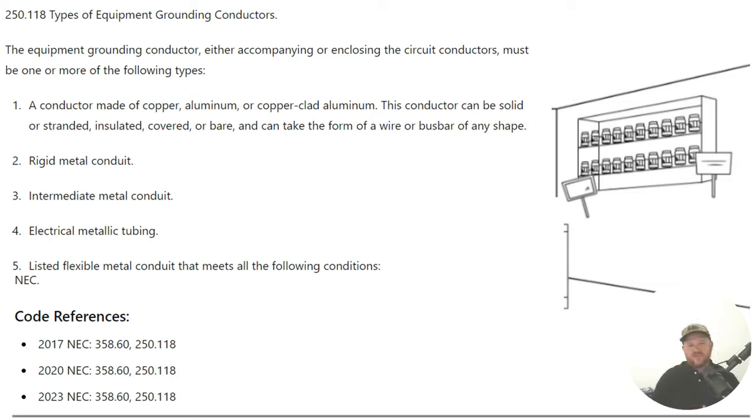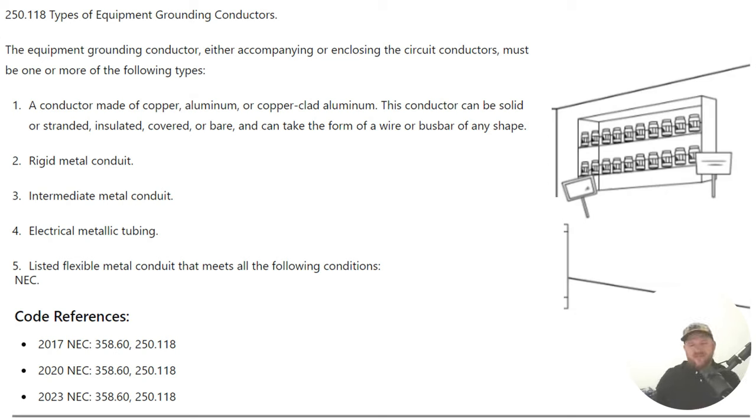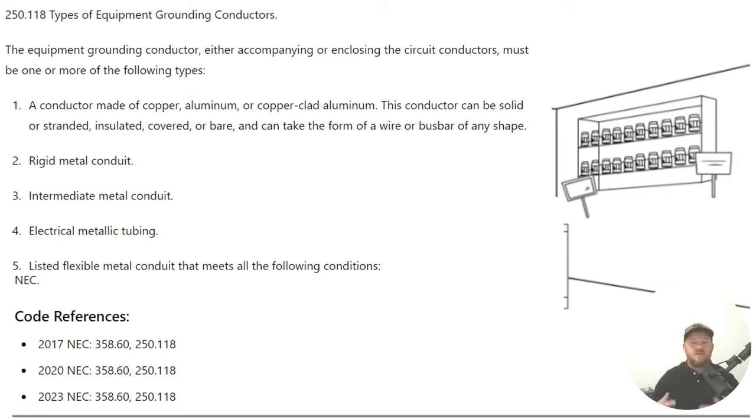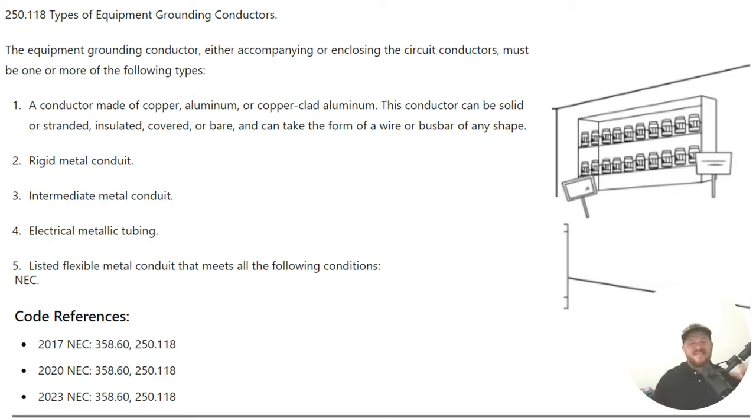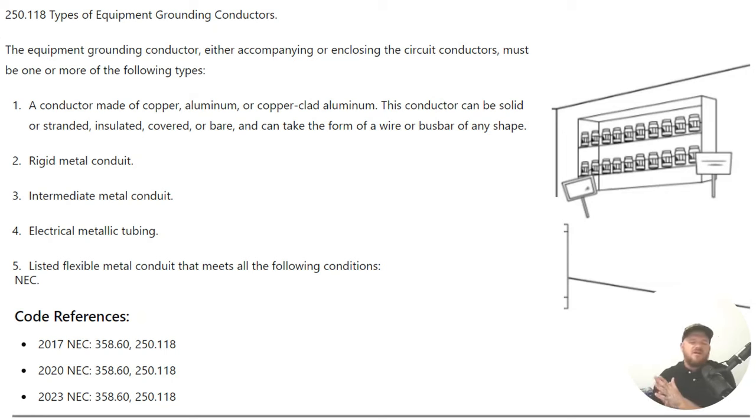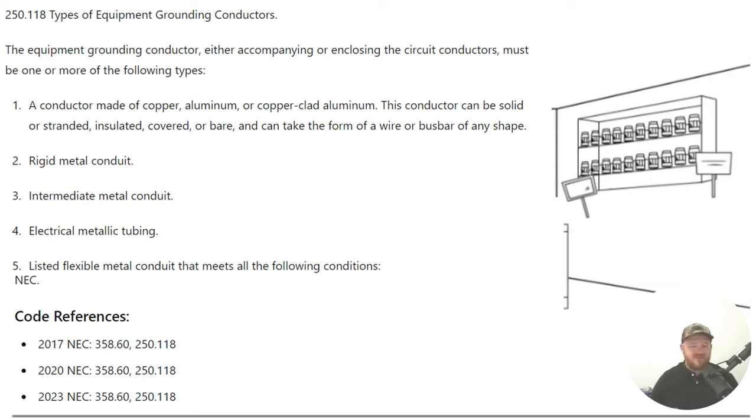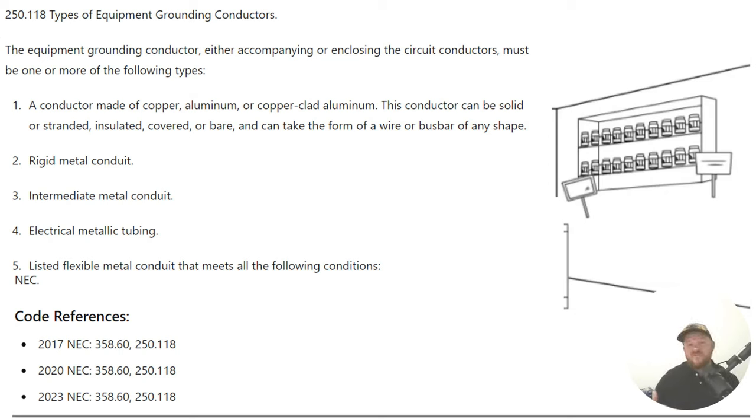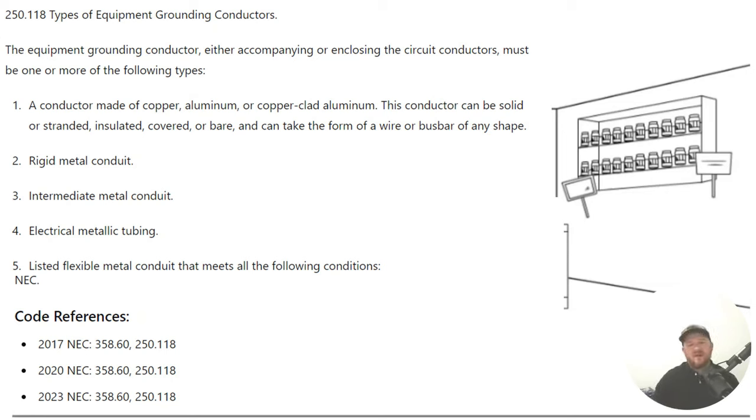I've only pulled five from this list, but it is a very long list of things that you might be surprised you can use as an equipment grounding conductor in lieu of a wire type. The second one is rigid metal conduit, the third one is intermediate metal conduit, and the one that we're talking about today is electrical metallic tubing, EMT. Then it goes on to talk about listed flexible metal and a bunch of other ones, but most of the rest of this list has special parameters that you're allowed to use or that you must abide by if you're wanting to use this as an equipment grounding conductor. So don't just think you're going to pull out some liquidtight flex and use it without meeting the other requirements that are listed there in 250.118.